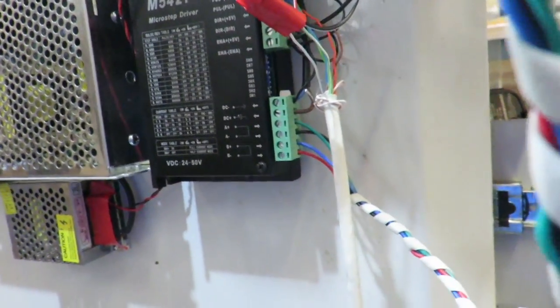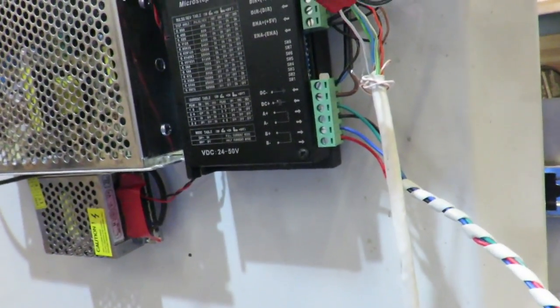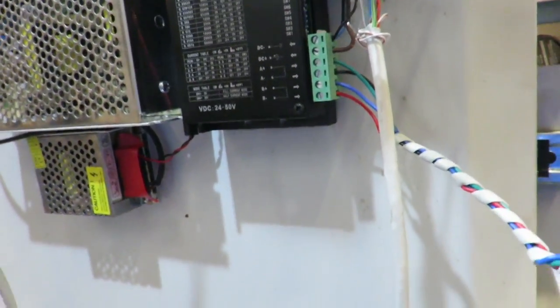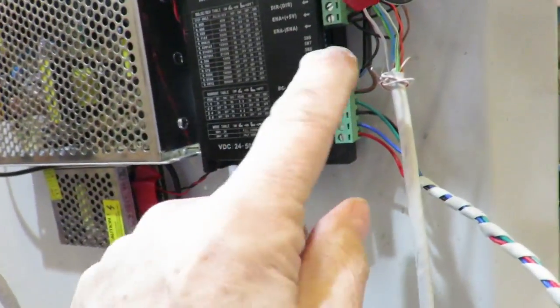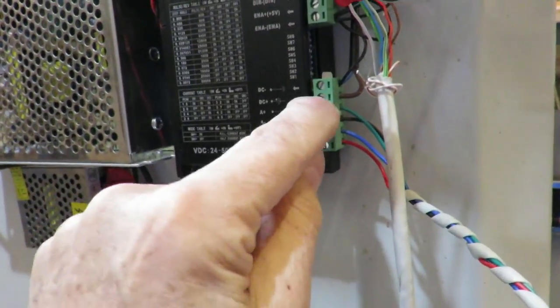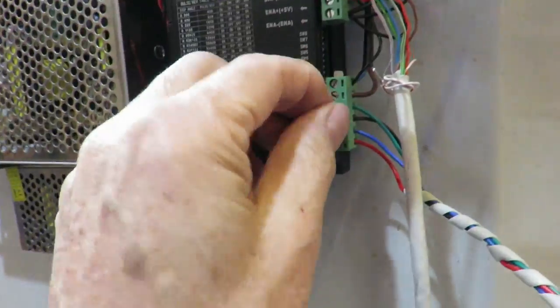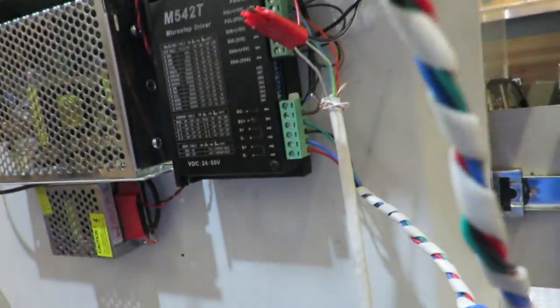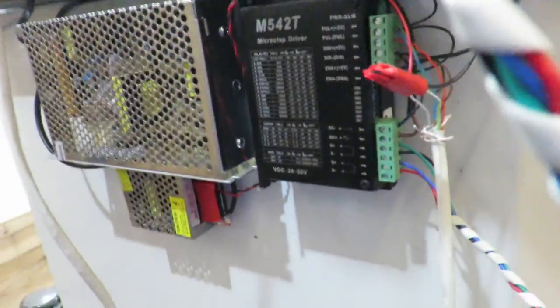So all you have to do is swap them back again. Easy to see. As soon as you try to traverse it right and it goes left, just swap any one of these. Any one of these pairs will fix that problem.